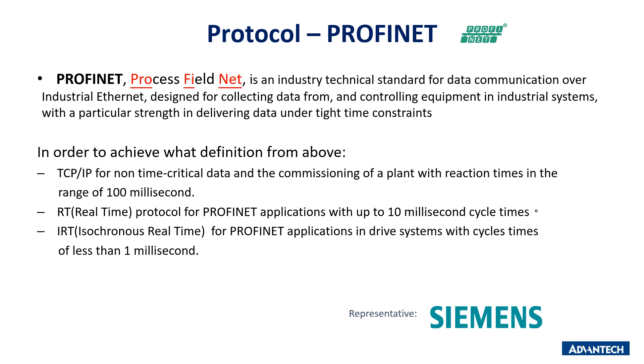Profinet, process field net, is an industry technical standard for data communication over industrial Ethernet, designed for collecting data from and controlling equipment in industrial systems, with particular strength in delivering data under tight time constraints. It achieves this through: TCP/IP for non-time-critical data with reaction times around 100 milliseconds; RT real-time protocol with up to 10 millisecond cycle times; and IRT isochronous real-time for drive systems with cycle times of less than 1 millisecond.